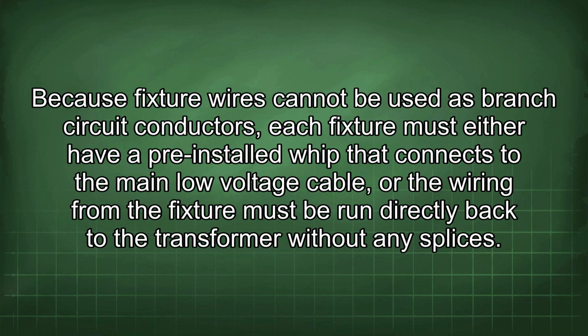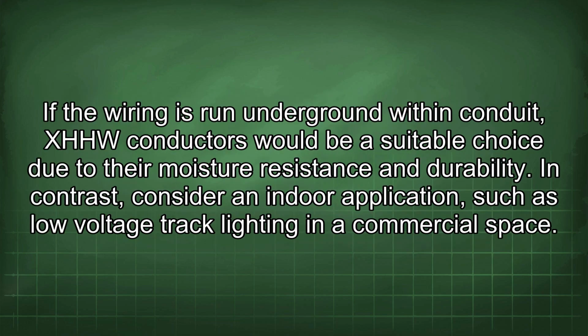Because fixture wires cannot be used as branch circuit conductors, each fixture must either have a pre-installed whip that connects to the main low voltage cable, or the wiring from the fixture must be run directly back to the transformer without any splices. If the wiring is run underground within conduit, XHHW conductors would be a suitable choice due to their moisture resistance and durability. In contrast, consider an indoor application such as low voltage track lighting in a commercial space.